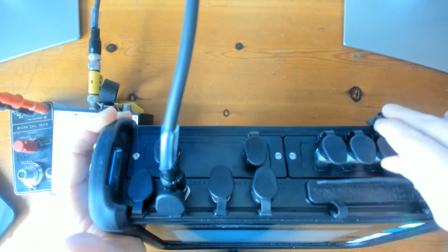Hello, this time I would like to show you how to connect a 4 to 20 milliamp sensor via the converter box into the HPM7000, and we will use some calculating channels to accomplish that. Usually, if we connect an analog sensor like a 4 to 20 milliamp sensor, we will be using the auxiliary input on the analog module. But let's pretend we don't have this module available. We will be using the standard CAN inputs on the base device.